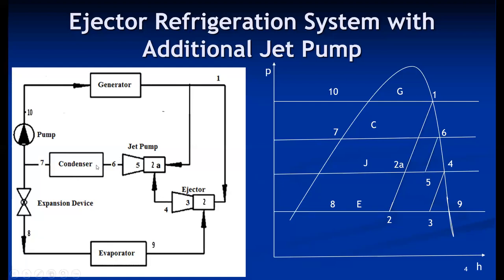From five to six, compression in the jet pump raises the pressure to the condensing pressure. Then six to seven is condensation in the condenser. At point seven, it divides into two streams: one goes through the pump to the generator — seven to ten is pumping — and the second stream expands through the expansion valve, seven to eight, then evaporates in the evaporator, eight to nine. Point nine and point two mix at point three. The first stream enters the generator at ten, evaporates from ten to one, completing the cycle. This is the ejector refrigeration system with additional jet pump, also called a multi-stage ejector refrigeration system.